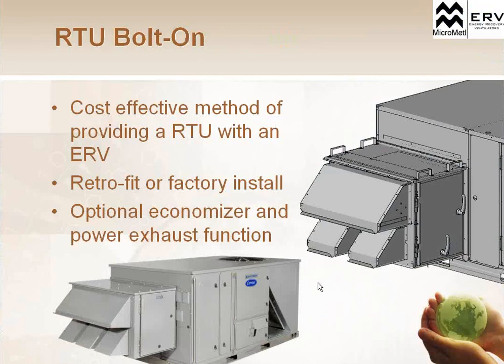Very easy to do. There are also bolt-on ERVs. So this would be your rooftop piece of equipment where you're supplying your economizer and your exhaust hoods would normally be here. We would remove those exhaust hoods and bolt on an energy recovery wheel to the side of the rooftop equipment. This is primarily for rooftops maybe 5 tons or less. So 2, 3, 4, 5 tons are small enough to have a system like this bolted on. The nice thing is that you don't have to worry about the roof curb below this system. It's small enough and light enough to just bolt directly onto the rooftop unit. So you'd have the optional economizer and power exhaust function with the system bolted onto the rooftop unit itself.